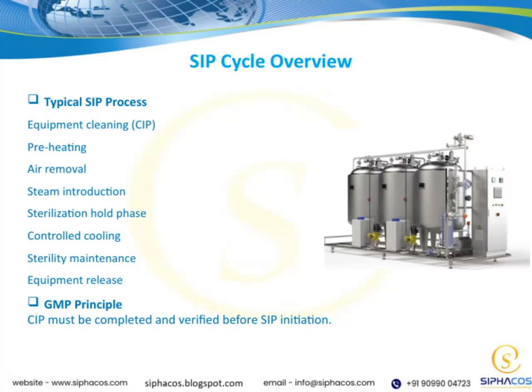Let's take a look at the typical SIP cycle, that's steam in place, and how it keeps equipment sterile. It starts with cleaning, or CIP, which must be done and verified before anything else. Then we move through preheating, air removal, and steam introduction. After that comes the sterilization hold phase, where everything is held at the right temperature. Finally, controlled cooling, sterility maintenance, and equipment release wrap up the process. This sequence ensures safety and compliance every step of the way.